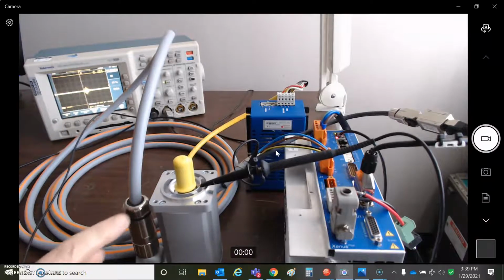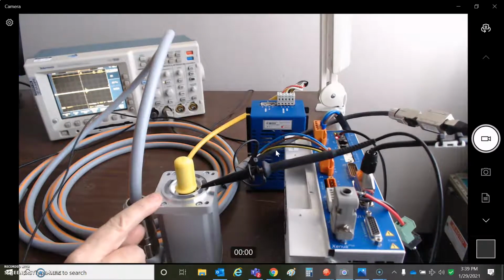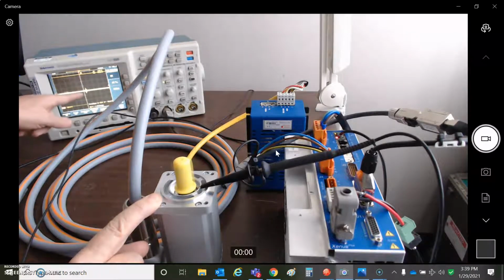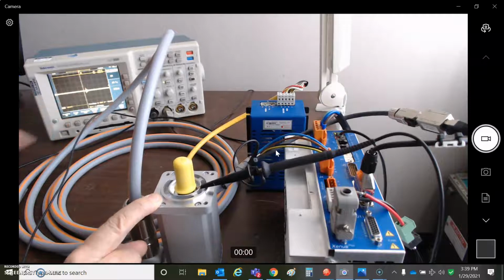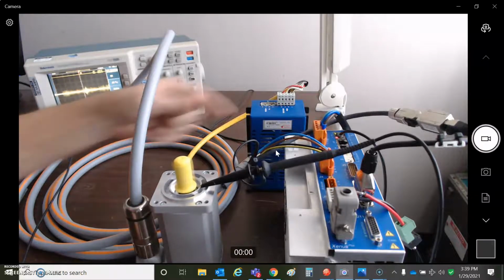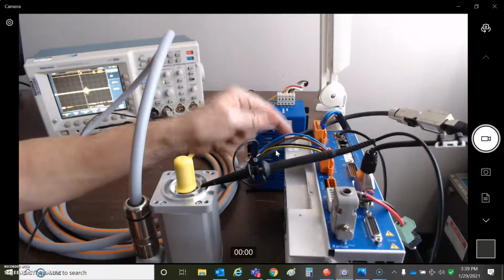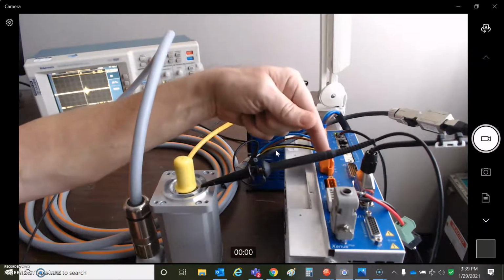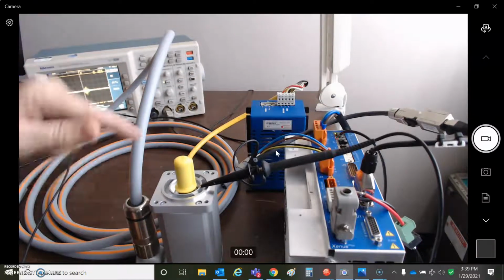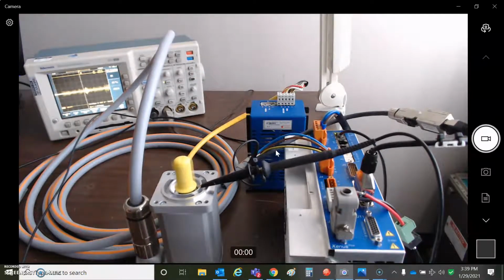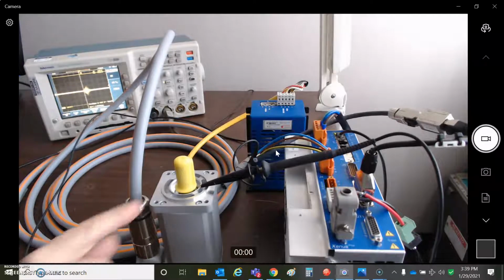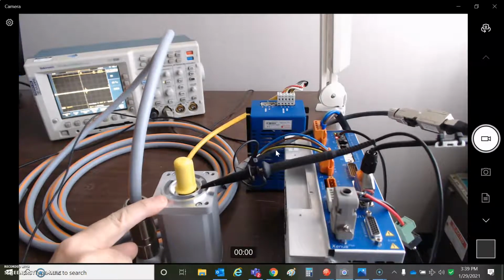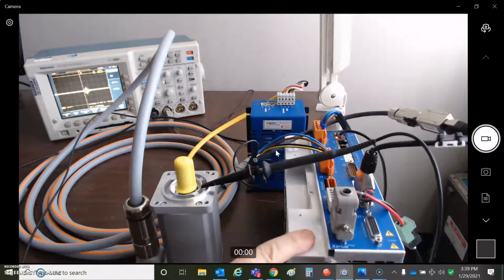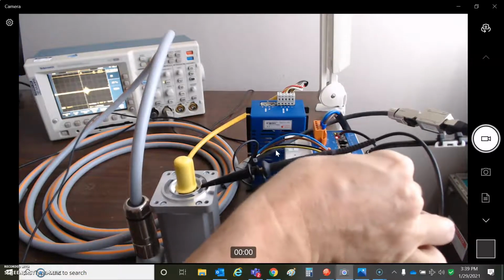Now, you also are supposed to ground the motor case. So when I bolt it onto the frame, I should have a good path to earth. You can see the amplitude coming down even further. It's 10 volts peak to peak now. So even though there is an earth connection at the drive, the frame should be connected to earth, and the earth goes to here, and it goes down this cable, and it gets connected. But that's a long cable. The electrons don't care. They just go everywhere. Okay, so motor case finds a good path to earth. Drive case should find a good path to earth. The feedback and connectors should find a good path to earth.